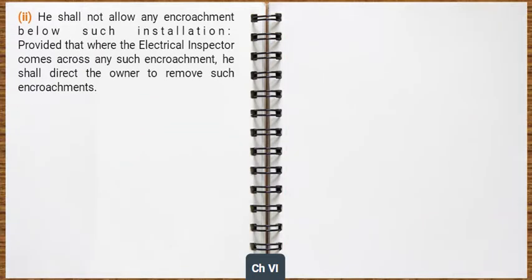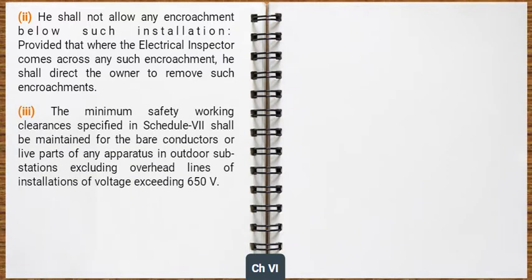He shall not allow any encroachment below such installation, provided that where the electrical inspector comes across any such encroachment, he shall direct the owner to remove such encroachments. The minimum safety working clearances specified in Schedule 7 shall be maintained for the bare conductors or live parts of any apparatus in outdoor substations, excluding overhead lines of installations of voltage exceeding 650 volts.